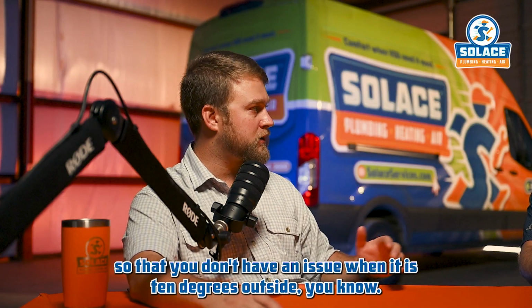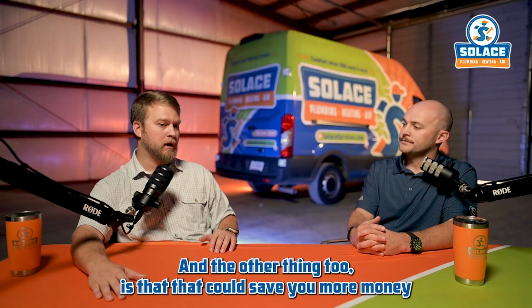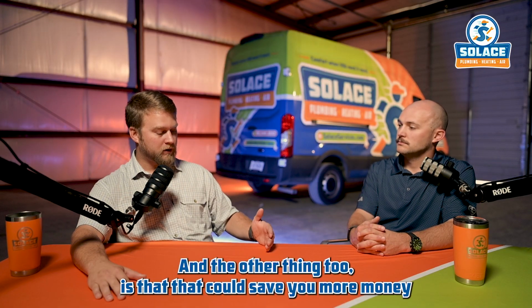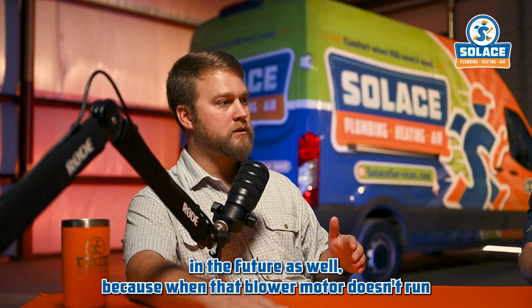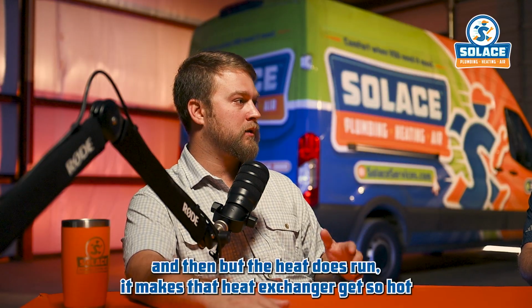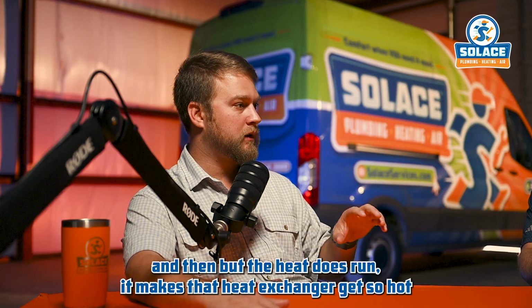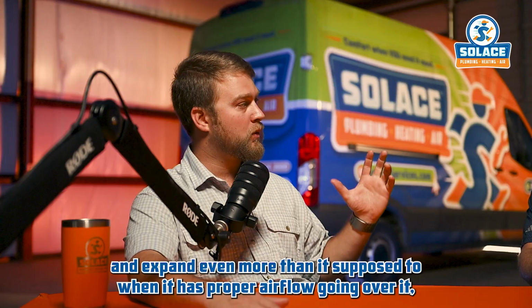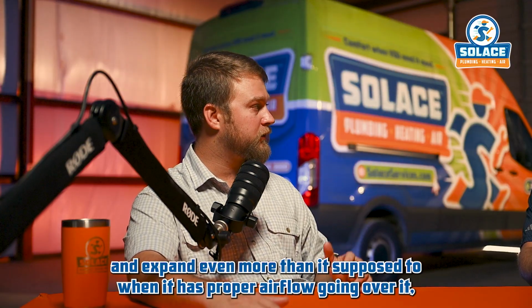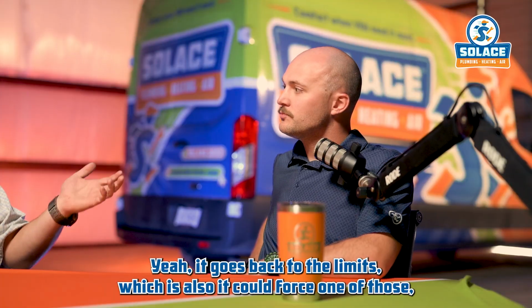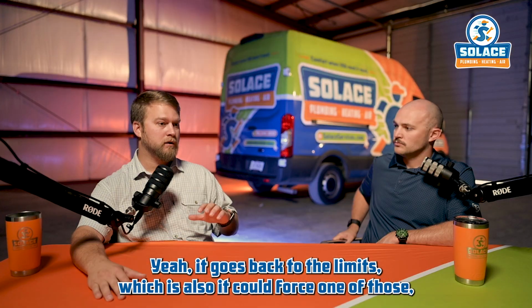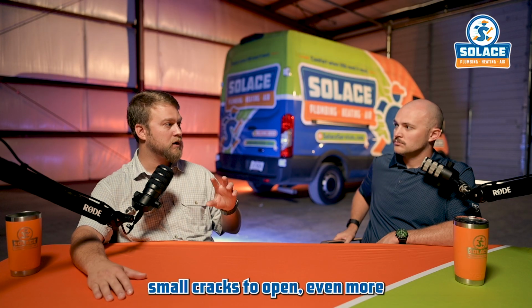you don't have an issue when it is 10 degrees outside. The other thing too is that it could save you more money in the future, because when that blower motor doesn't run but the heat does run, it makes that heat exchanger get so hot and expand even more than it's supposed to with proper airflow going over it. It goes back to the limit switch, and it could force one of those small cracks to open even more.